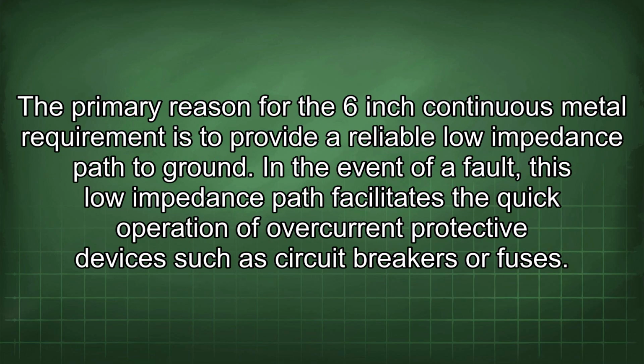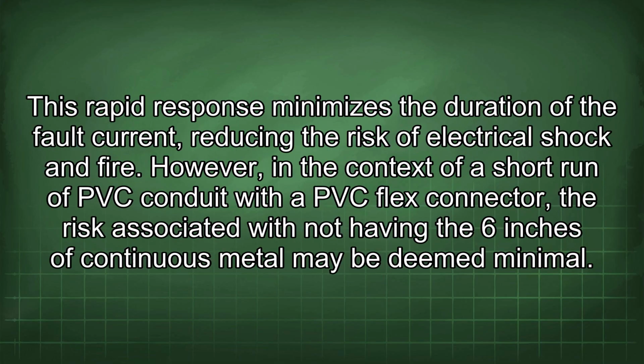The primary reason for the 6-inch continuous metal requirement is to provide a reliable low-impedance path to ground. In the event of a fault, this low-impedance path facilitates the quick operation of overcurrent protective devices such as circuit breakers or fuses. This rapid response minimizes the duration of the fault current, reducing the risk of electrical shock and fire. However, in the context of a short run of PVC conduit with a PVC flex connector, the risk associated with not having the 6 inches of continuous metal may be deemed minimal.